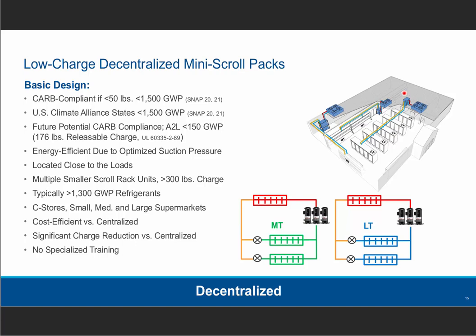And because of that, with this decentralized architecture, you're able to optimize suction pressures to drive efficiency. So if you've got a plus 20 degree loop, you put them on a plus 20, you keep the suction pressure as high as possible, and you keep your energy savings as high as possible. So that's another big advantage. And also, when you compare the charge, in our image here you've got three separate charges. So if you have a leak, it is contained to one of those circuits, not the entire system. So there's certainly advantages there as far as that goes.